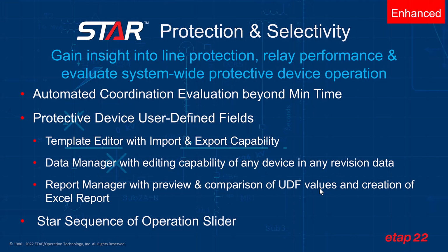Star protection and selectivity allows you to gain insight into line protection, relay performance, and evaluate system-wide protective device operation. AutoStar, or Automated Coordination Evaluation, has been improved to allow you to do this evaluation beyond the minimum time. And all protective devices now support user-defined fields. These user-defined fields allow you to extend each component, such as a relay, fuse, or low voltage circuit breaker, and include parameters for those devices that are not commonly used in protection and selectivity.